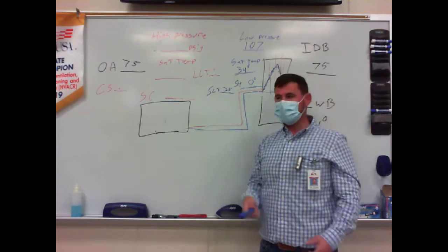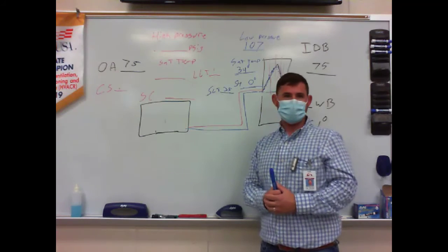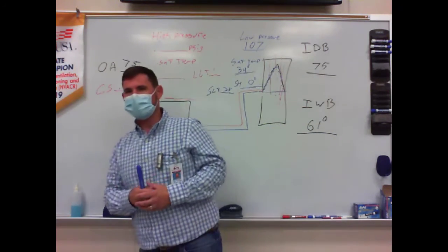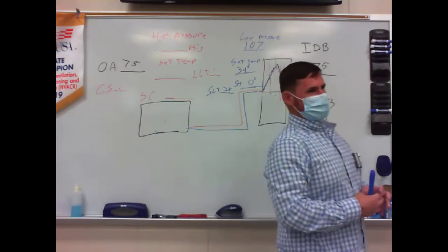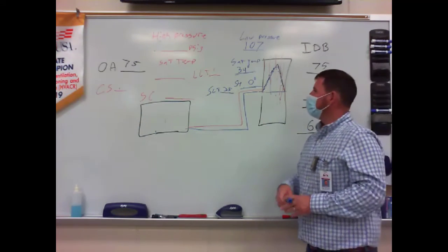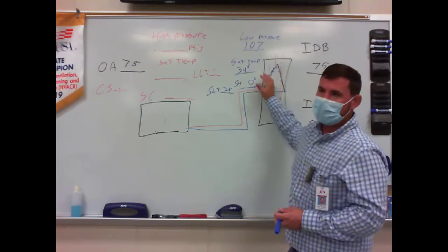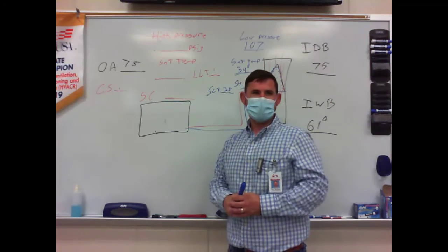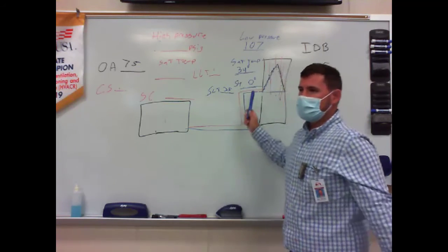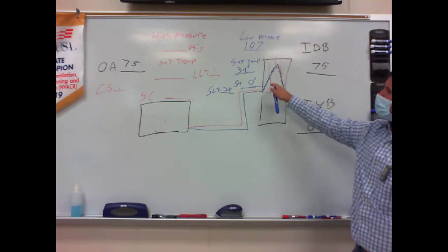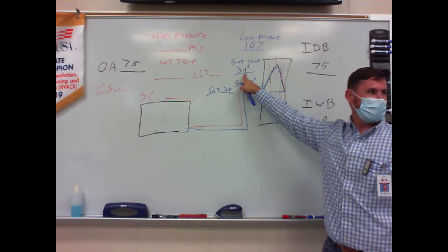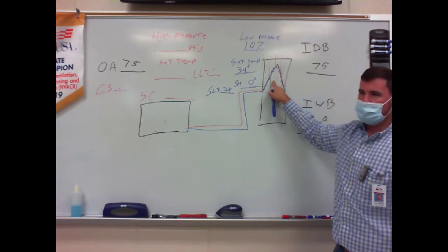Bubba's just used to seeing pressures, and when they ain't there, he either adds refrigerant or he takes it out, right? We don't want to be like Bubba. There's some good Bubbas out there, don't get me wrong. But the one I'm using in my example is a bad Bubba. That's why it's important for us to understand all the dynamics of these systems before we just start dumping refrigerant in. So if it were me looking at this, I would say, because that number's so low, I can't take more refrigerant out. Can I add more heat to it?